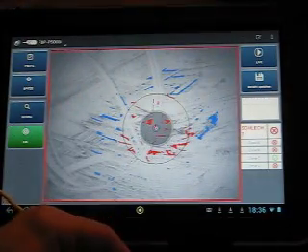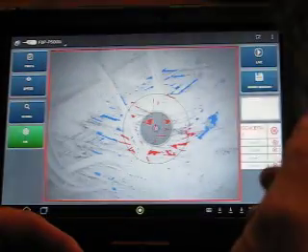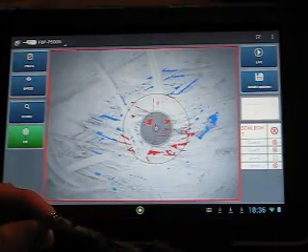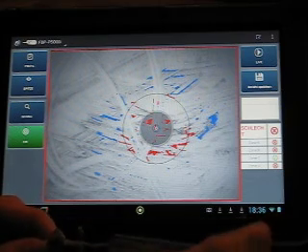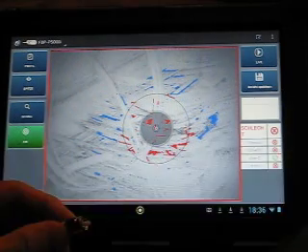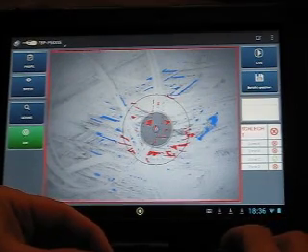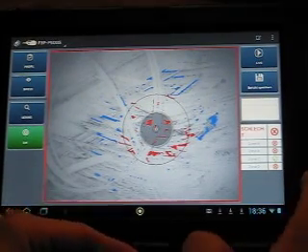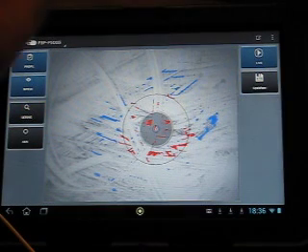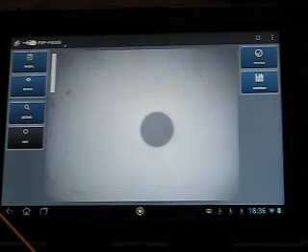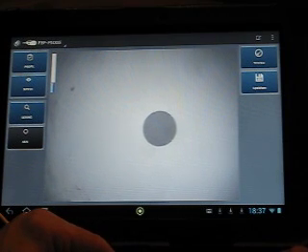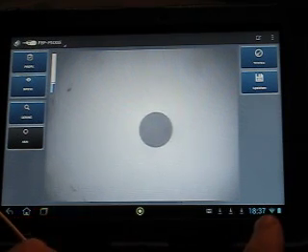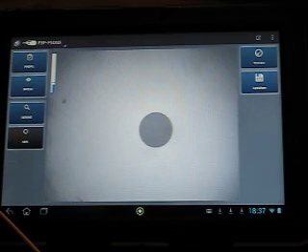I try to clean him. I take this cleaning tool. After connecting again, I have to go live back and I see that it looks quite nice. Can check for the focus, it's okay. I can do an auto center as well, test again.